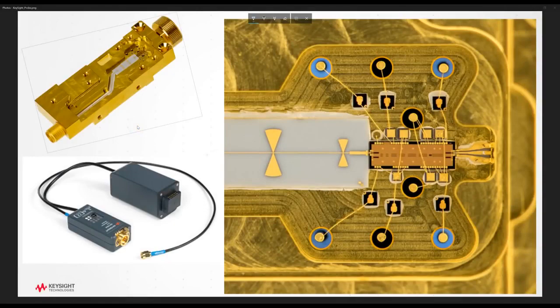And here is what is inside this calibrator probe. This module that we were just looking at, this is what it looks like on the inside. There is an IC in the front, which we will take a look at in just a second, and there's a signal deck which can be fed directly into this IC. This signal is going to come from the auxiliary port of the oscilloscope itself, which generates a square wave. The rise time of that square wave is nowhere close to 110 gigahertz equivalent bandwidth. So you're going to have to increase the edge sharpness and reduce the rise and fall times before it becomes useful for doing NIST calibration up to 110 gigahertz, which is exactly what this is.